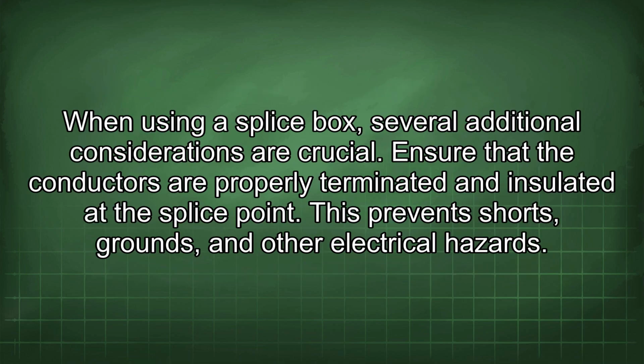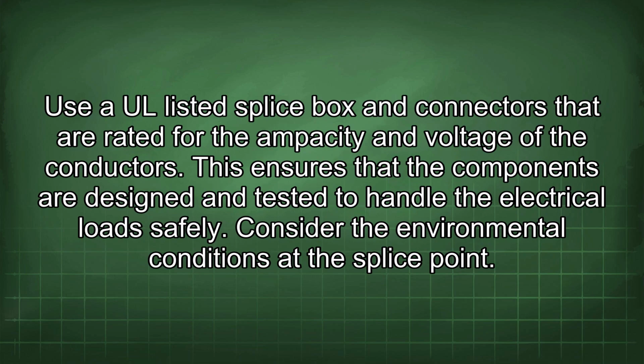When using a splice box, several additional considerations are crucial. Ensure that the conductors are properly terminated and insulated at the splice point. This prevents shorts, grounds, and other electrical hazards. Use a UL-listed splice box and connectors that are rated for the ampacity and voltage of the conductors. This ensures that the components are designed and tested to handle the electrical load safely.